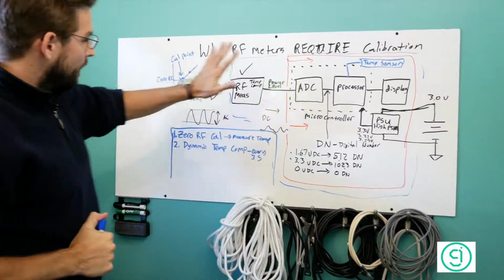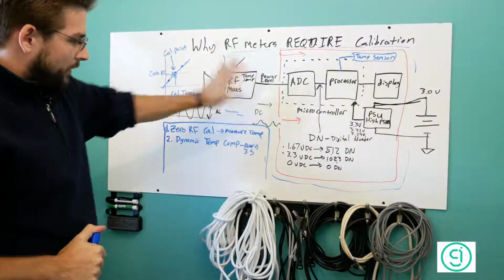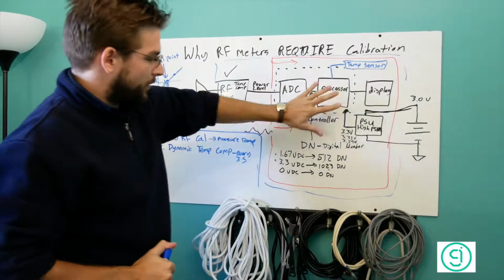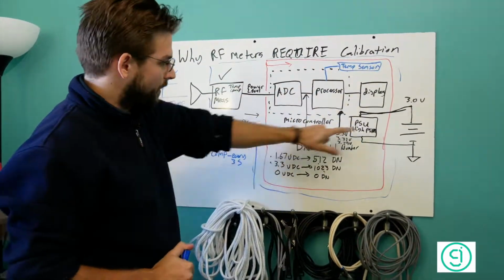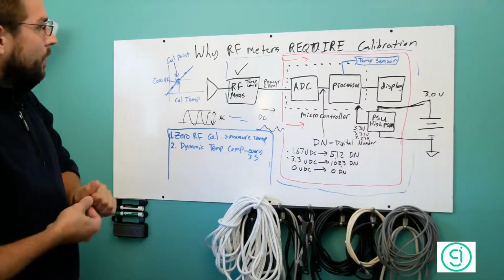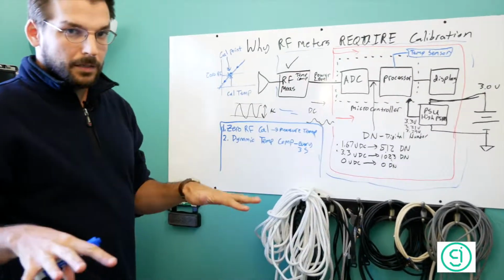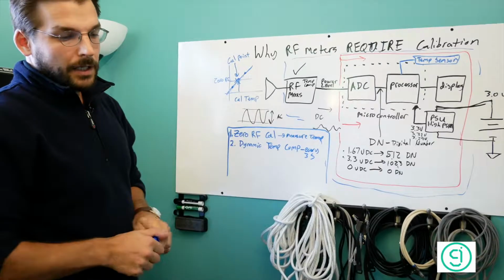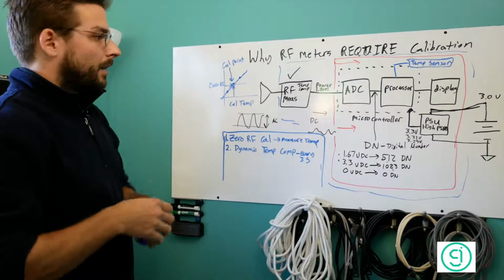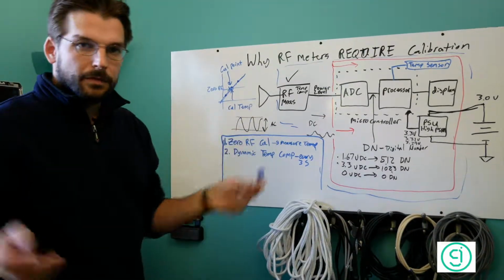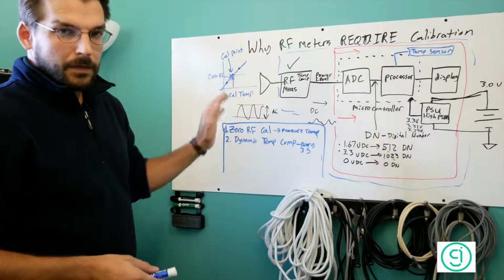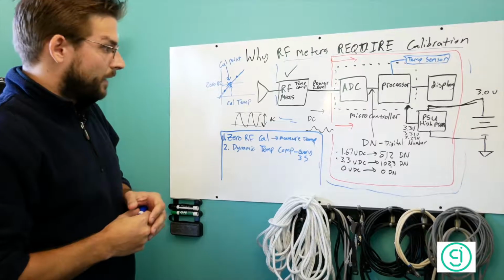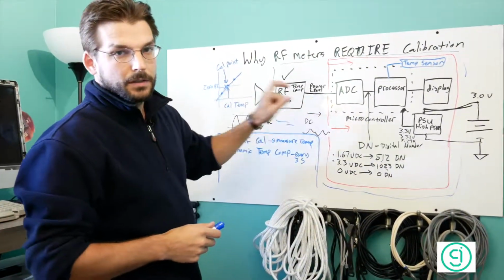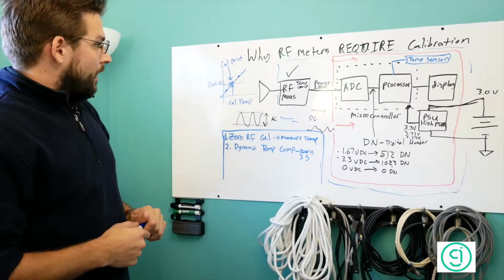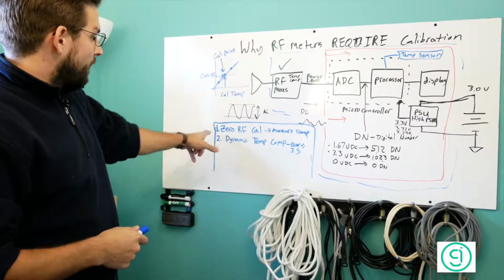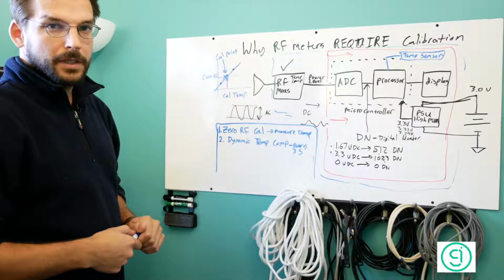Anyway, this has to do with all of the rest of the subsystem. Even if you have a temp compensated RF measurement subsystem, you have to temperature compensate and calibrate the rest of the device because there's all these other variables that affect your measurement. Now, this is only an issue if you're trying to measure with high precision. If you're not, then you're talking about a lower end device. You can buy these $100, $50 devices, and they won't do any of this stuff. But when you start spending real money on a really good meter that measures precisely, the meter has to do this. Otherwise, your values will not be accurate across temperature, they won't be accurate across different measurement conditions, and they won't be accurate between meters. So you have to do RF calibration on every single meter that leaves your factory.